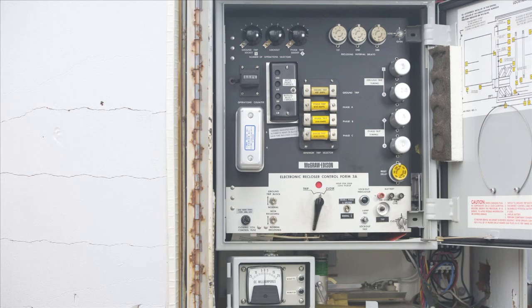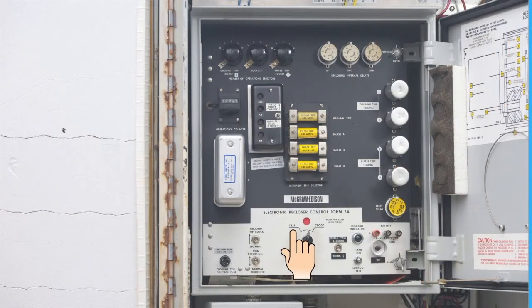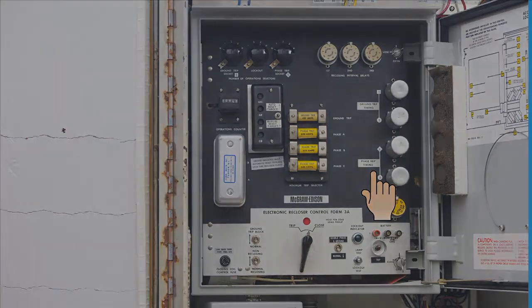If the fault is permanent, the control performs its complete programmed sequence of recloser commands and locks out with the recloser open. Once locked out, the control must be manually reset to the start of its operating sequence, which simultaneously closes the recloser. Factory-calibrated timing plugs establish the time current characteristics for both phase and ground tripping. 2 sets of individual timing curves provide dual timing for both phase and ground.